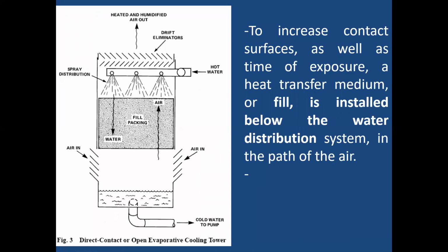Now, in order to increase the contact surface as well as the time of exposure, a heat transfer medium or fill is installed below the water distribution system in the path of the air. Such a package is used in the cooling tower, and the main purpose is to provide more surface for cooling as well as more time for the heat transfer medium, that is air. So the closer the fill package, the more time is spent in this fill package, this particular portion, and the more range we can get.